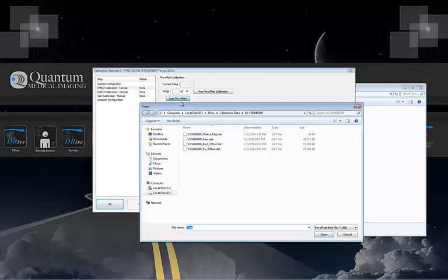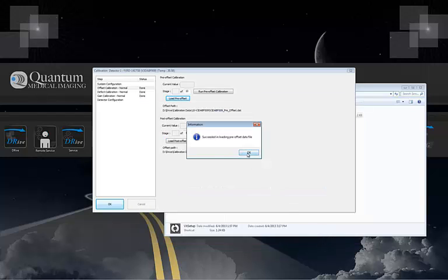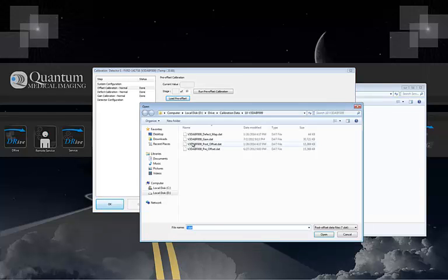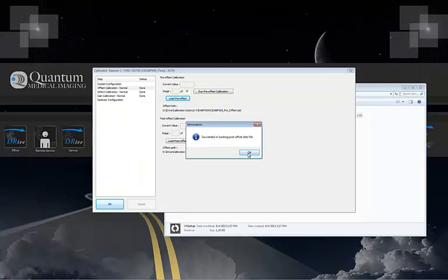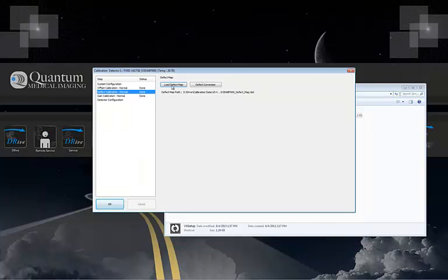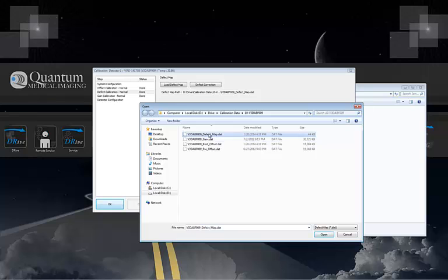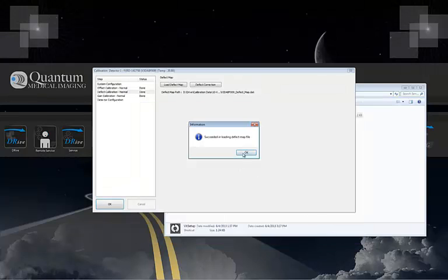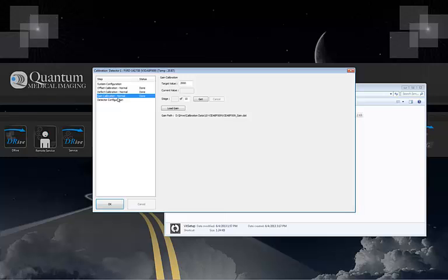Under the offset calibration, instead of a field calibration, you'll see me pointing to the detector factory calibration for pre and post offset. Similarly, for defect calibration, pointing to a factory calibration. And finally, for gain calibration.